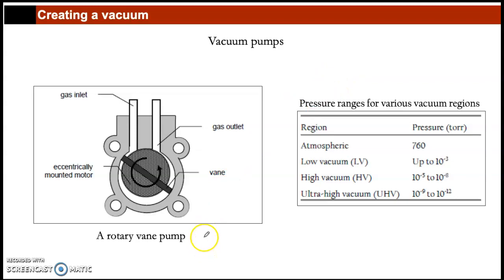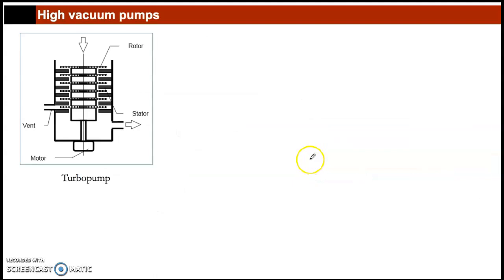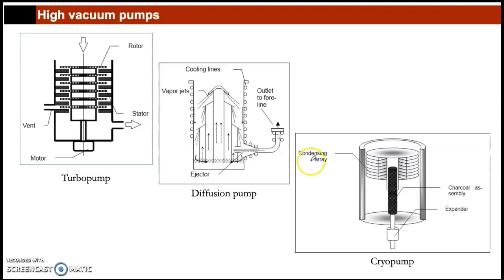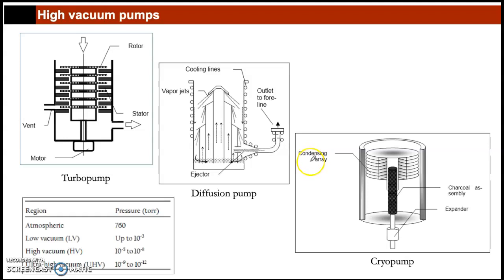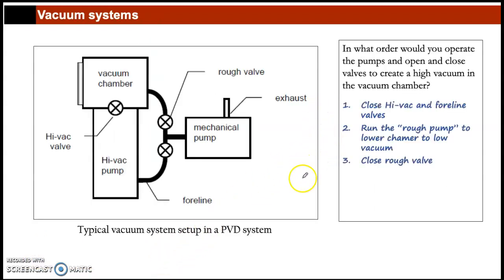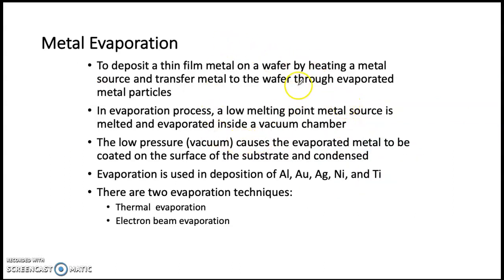To create a vacuum, we need pumps. One type is the rotary vane pump, which can reach pressures down to 10⁻³ Torr depending on the application. For higher vacuum, there are turbo pumps, diffusion pumps, and cryo pumps — these can achieve high vacuum and ultra-high vacuum levels.